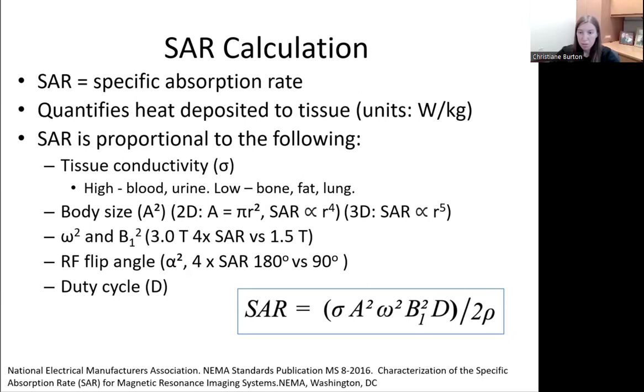SAR is proportional to the square of the RF frequency. Typically, the RF frequency is chosen to closely match the Larmor frequency, which in turn is directly proportional to the static main magnetic field of the main magnet. So, all things being equal, SAR depends on the square of the main magnetic field and of B1. So the same pulse sequence for the same patient imaged at 1.5T would therefore generate 4 times the SAR if performed at 3T. SAR is proportional to the square of the RF flip angle.